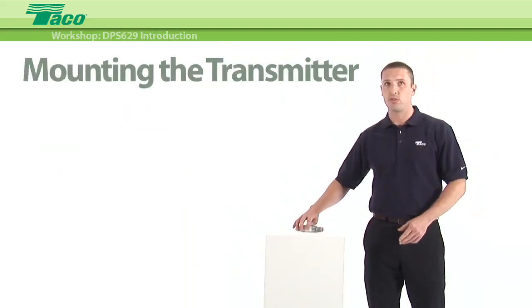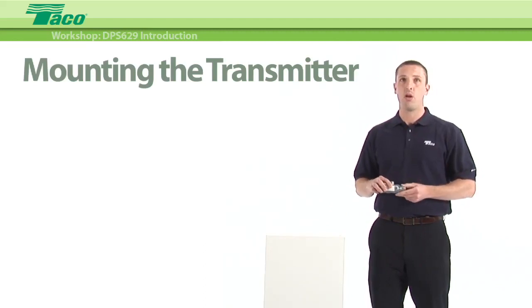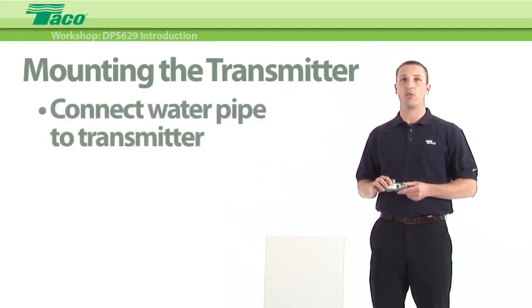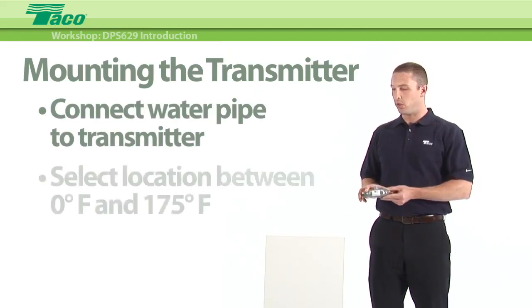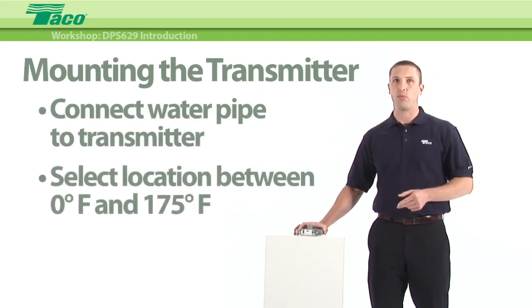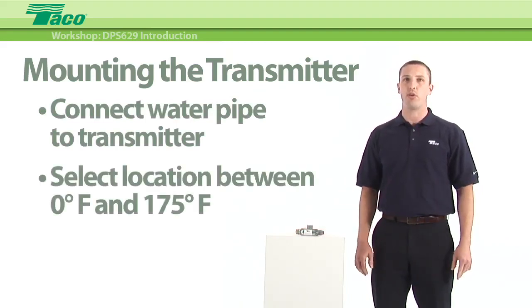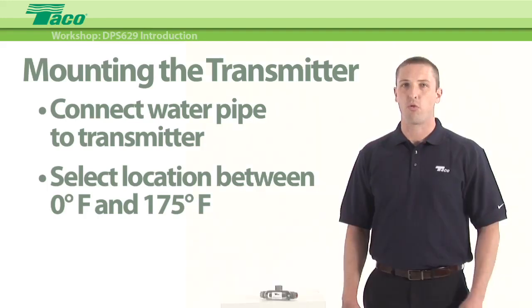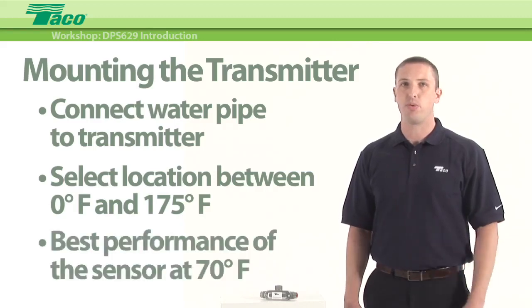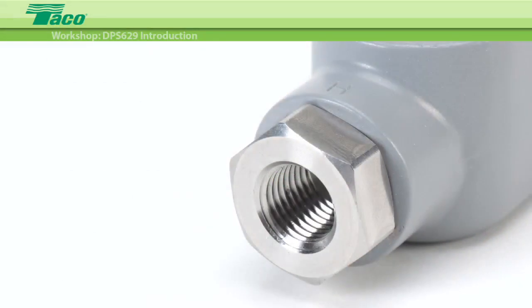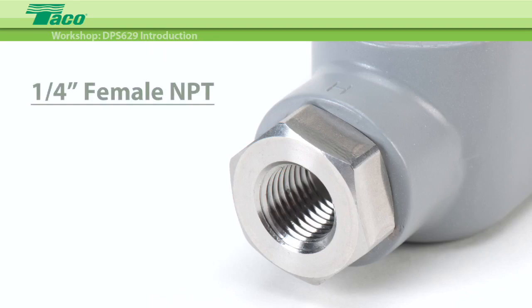Since the process fittings of the transmitter are fixed in place, plan to connect the process water piping to the transmitter first. Select the location where the temperature of the unit will be between 0 and 175 degrees Fahrenheit and will not be subject to excessive shock or vibration. For optimal performance of the sensor, it should be used in an area where temperature will be maintained near 70 degrees Fahrenheit. The process connection on the DPS629 is 1/4 inch female NPT, so the mating end of the process piping must be a 1/4 inch male NPT.